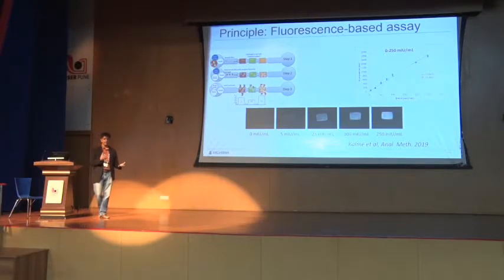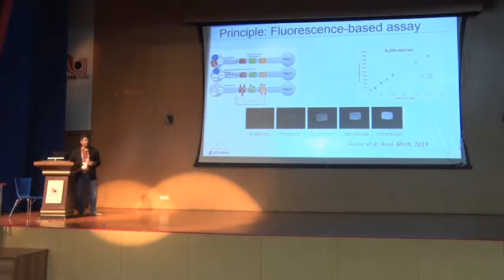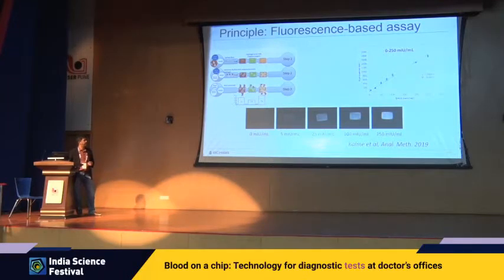So that's why the microfluidics has become important here for the miniaturization reason that I said earlier, that you have a very small volume of blood, more like 0.02 ml, an order of magnitude less, but you still want to get all that information from it. So can you do that? That 0.02 ml of blood, basically 20 microliters, flows through here, and we do some simple binding immunofluorescence chemistry that generates a fluorescence readout, and we use that to report the values of hormones on our platform.